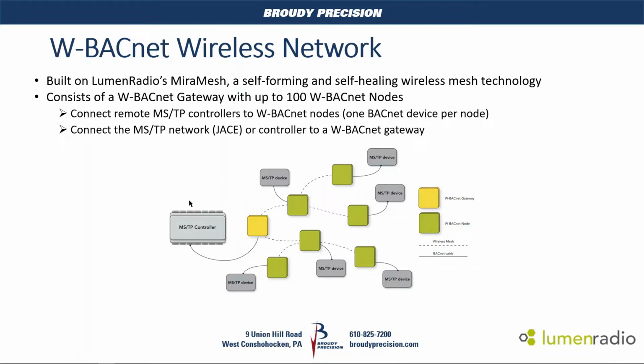As the picture dictates here, we have a gateway that's marked being yellow here. The W-BACnet device as a gateway tied to an MSTP network of controllers, a JACE, whatever you might have. And then all the remote MSTP devices are connected to a W-BACnet node. Same part number, just set up as a node, and it's one device to each node. You can have up to 100 of these W-BACnet nodes on a mesh network, and basically it's to connect remote MSTP controllers to a network of controllers.